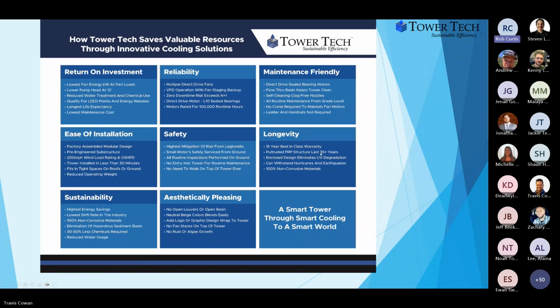A pretty exhaustive warranty. We expect 35 plus years out of the tower. From a sustainability standpoint, I think a reduction in the chemical treatment cost, reduction in carbon footprint because we reduce energy required. And then our variable flow self-cleaning nozzle has a sustainability about it that once you put the cooling tower in, it holds its performance throughout the life, as opposed to something getting dirty and you lose performance and you don't know it. And so it can't sustain its original design performance unless you go do something to it. TowerTech's able to sustain it for much longer periods of time. We'll see something in a minute.